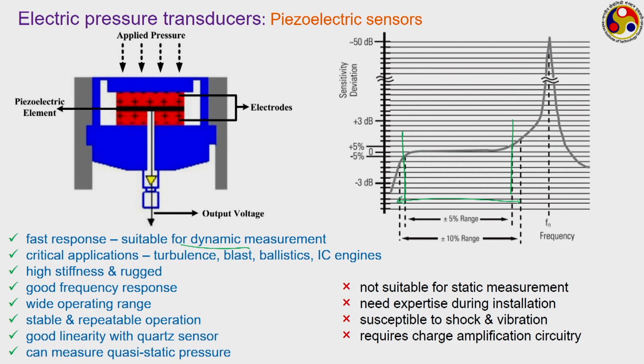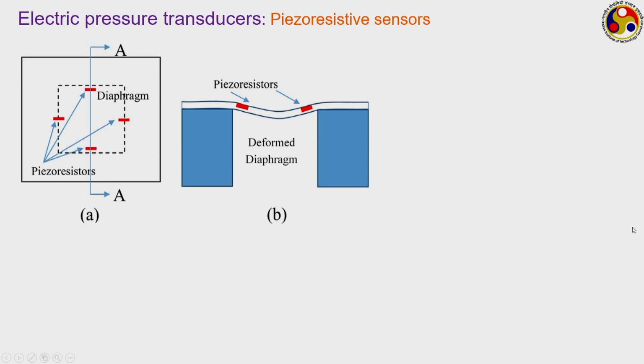They require charge amplification circuitry, because the charge that we get corresponding to general pressure levels can be quite small, and somehow you have to amplify that to get a measurable output voltage. And if they are subjected to some kind of overloading, there is a possibility of failure of the crystal itself, permanent damage to that. So, we must adhere to the specified operating region. But still, piezoelectric sensors, like any other piezoelectric based measuring devices, are again a very good option for pressure measurement. There is another variation of piezoelectric sensors, which is the piezoresistive sensor.